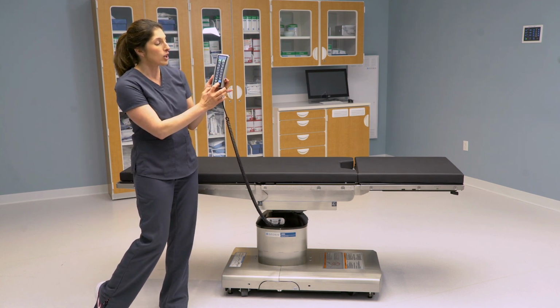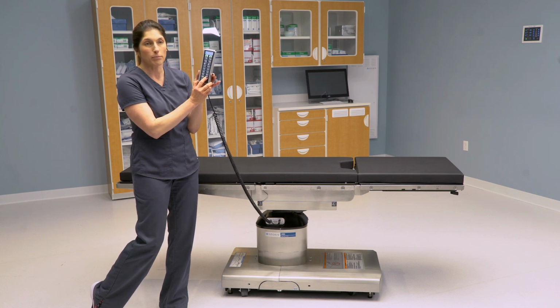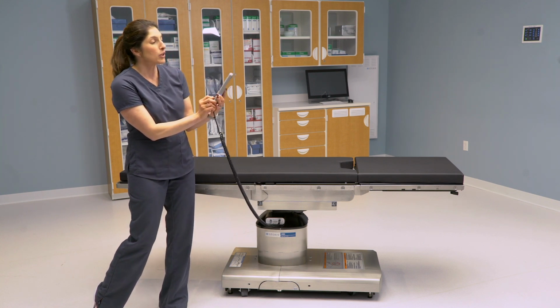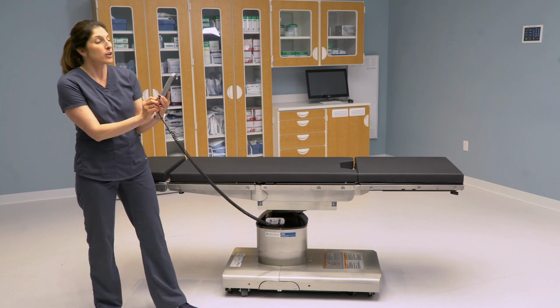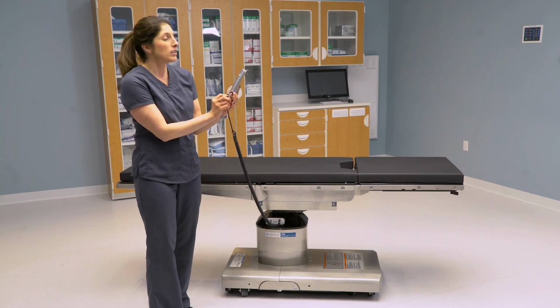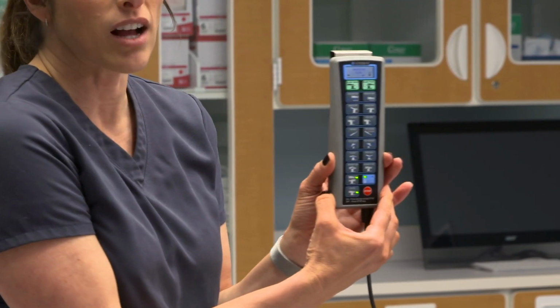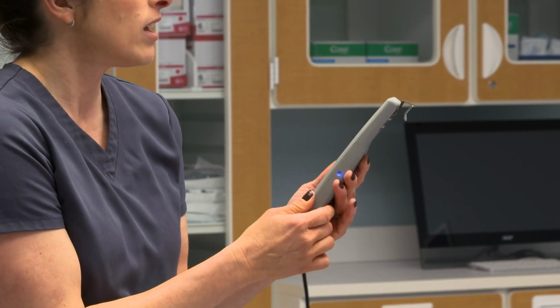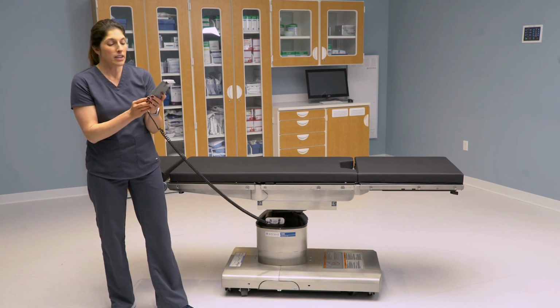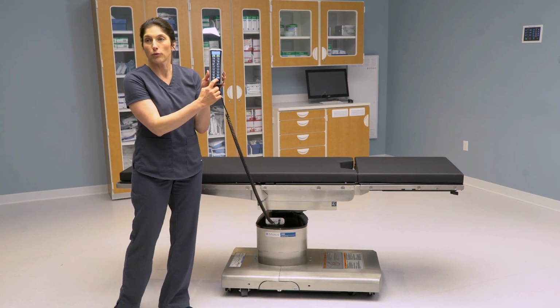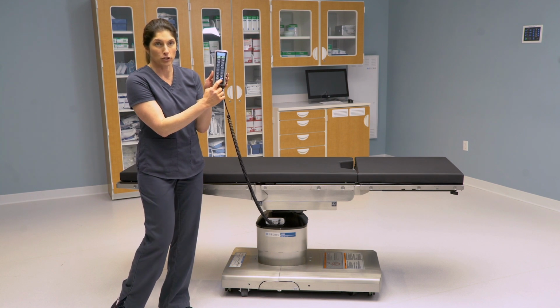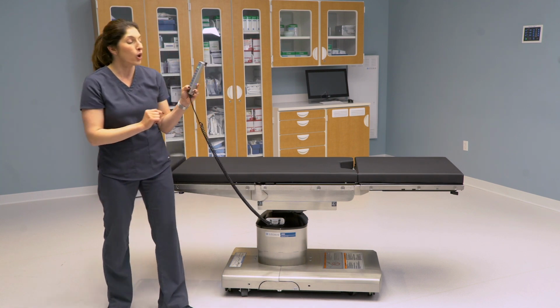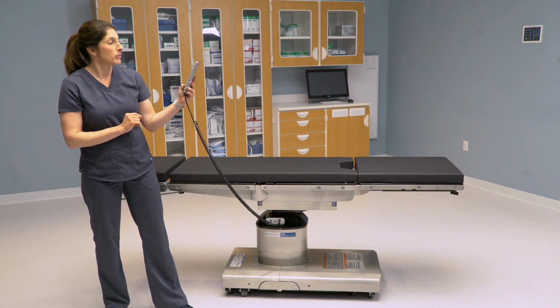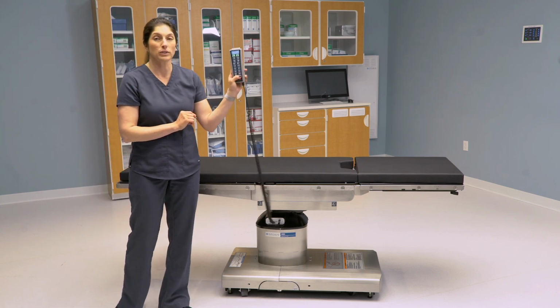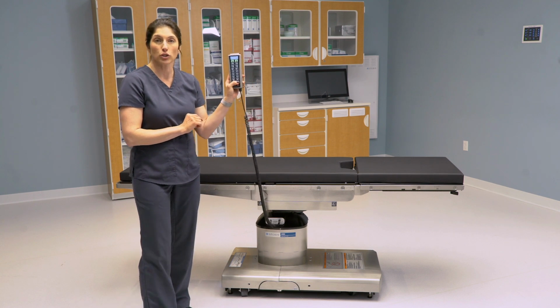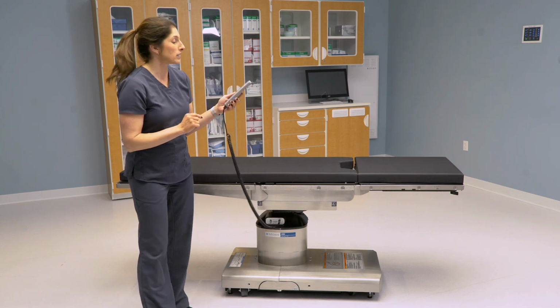On the 4085, you just press and hold the blue floor lock button, and the screen will tell you hold 3 seconds to unlock. And there is a green padlock that will then turn into an orange open padlock, and the screen will say unlocking. And then you'll know your table is unlocked. Then you also have an orange indicator light on the floor lock showing that you're in the unlocked position. You can press and hold floor lock, and it will say hold 1 second to lock, and then it'll tell you it's locking. So if at any point you're not sure, check the LCD screen and it will indicate what you're doing.